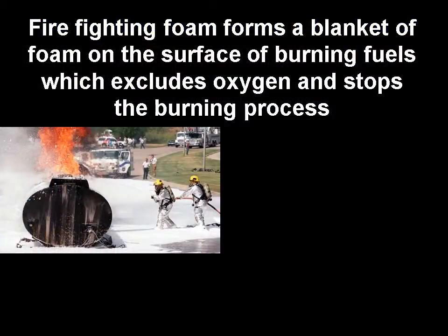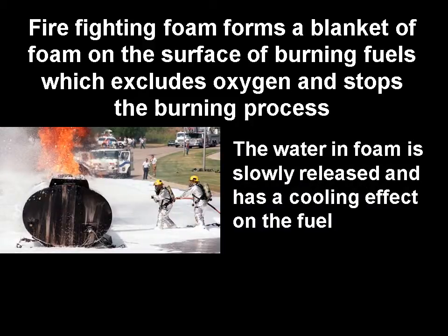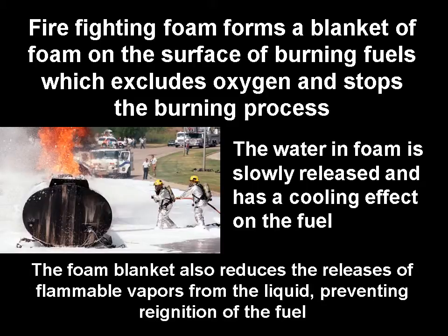Firefighting foam forms a blanket of foam on the surface of burning fuels which excludes oxygen and stops the burning process. The water in foam is slowly released and has a cooling effect on the fuel. With ignitable liquids, a foam blanket also reduces the release of flammable vapors from the liquid, preventing reignition of the fuel.